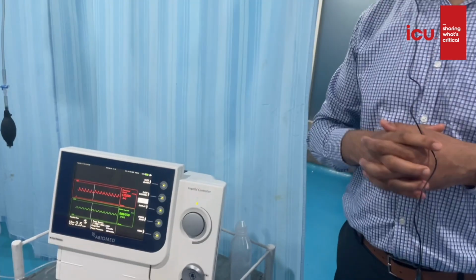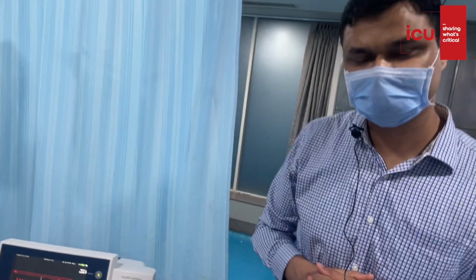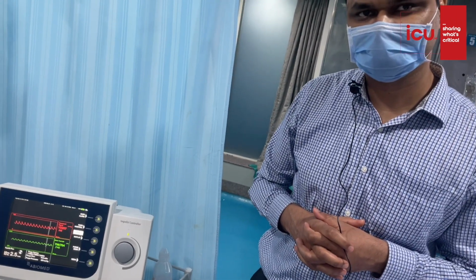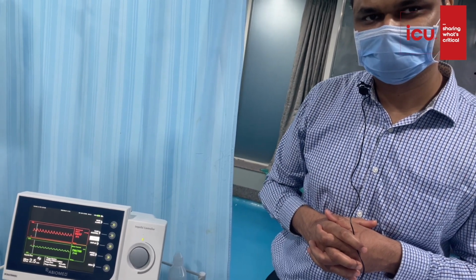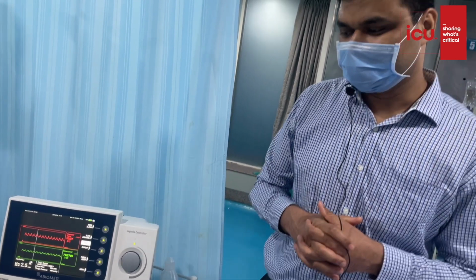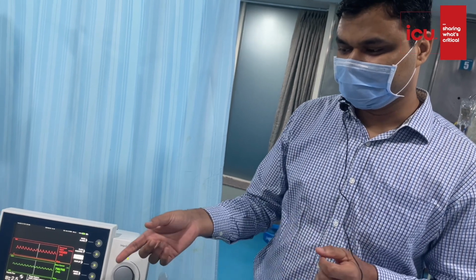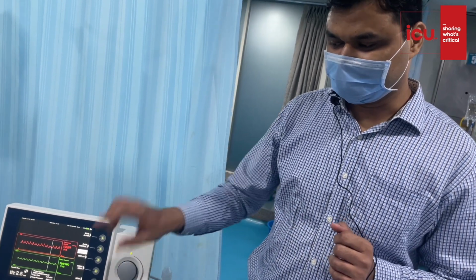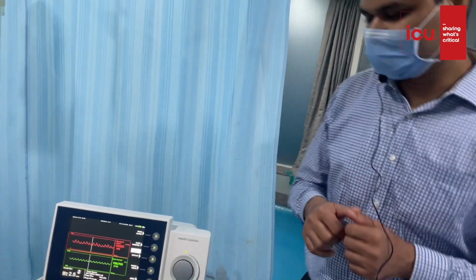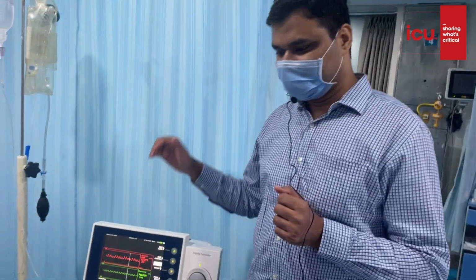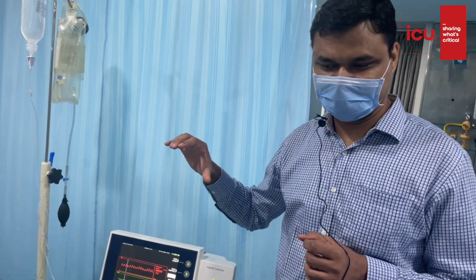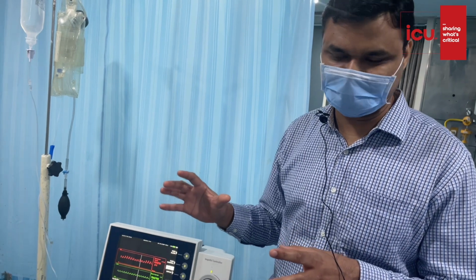So my question is, if by any chance we put saline in it, will it hamper the functioning of the motor? You mean the normal saline replaced by dextrose, or dextrose replaced by normal saline? In the purge system, if we replace dextrose by saline. Yes, so that's a very great question. So when it comes to the purge, we always recommend to use dextrose because dextrose has the right viscosity that helps to maintain the health of the motor, which is a very sensitive part of the Impella device.